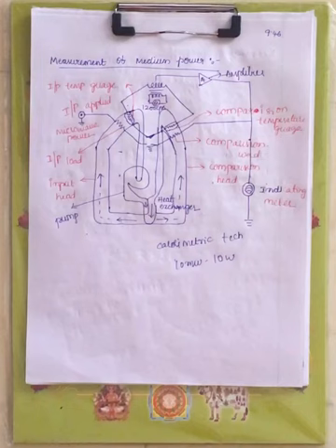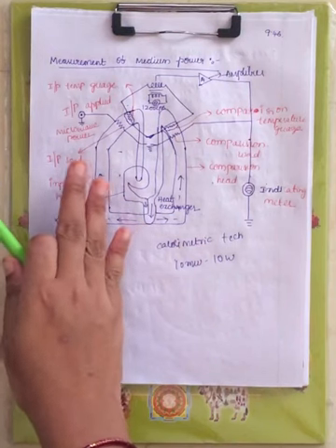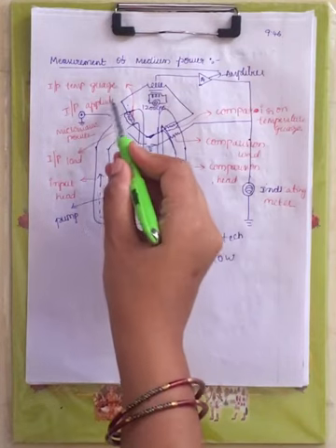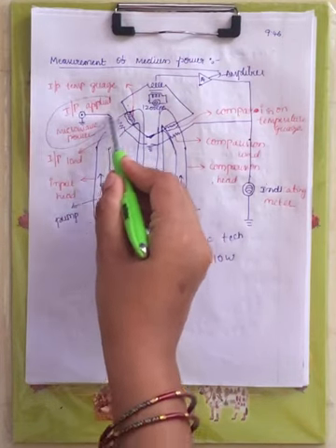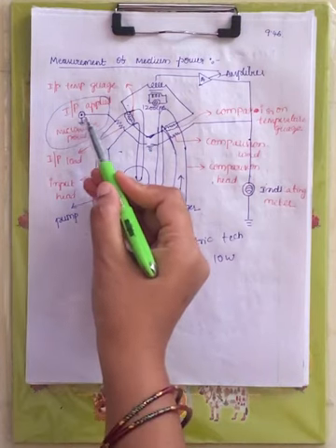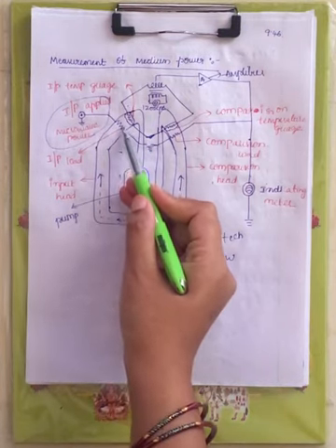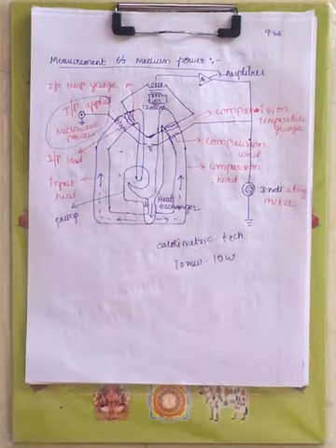Now this is the structure through which we will measure the medium power. If you see this structure, it contains two heads. One head is where you give the input, the applied microwave power that you want to measure. It is given at this point, and this is connected to this particular resistance. We call it the input load.